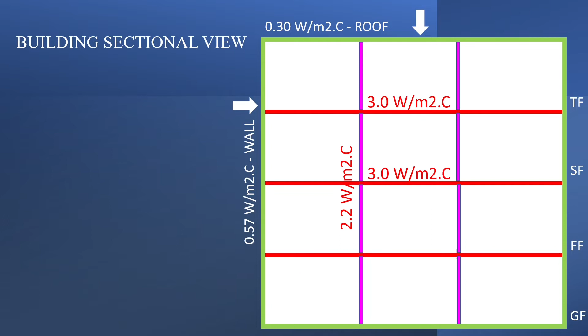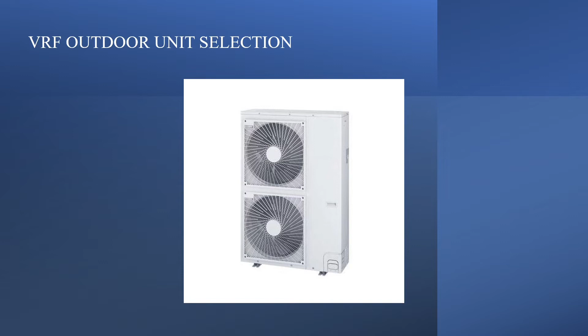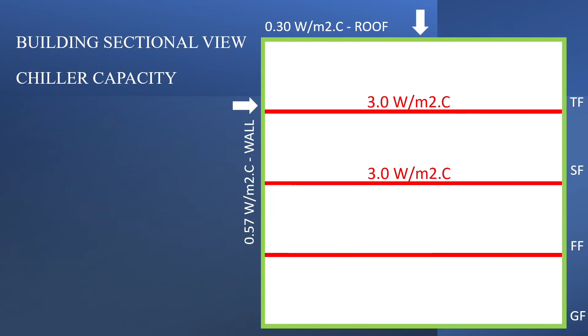Now, when the supplier selects the outdoor unit, the capacity may be further increased as the supplier does not have the same capacity outdoor unit based on actual requirements. What happens when the designer makes calculation for the capacity of the chilled water system? While doing high side chilled water calculation, flat partition, corridor partition, lower level and upper level floor need not be considered as a partition. Now, some of you may be wondering, does the partition load have a real impact on load calculation? Of course, yes.